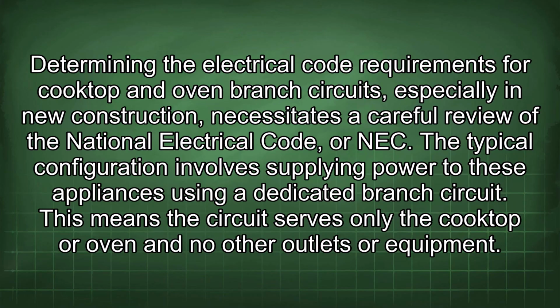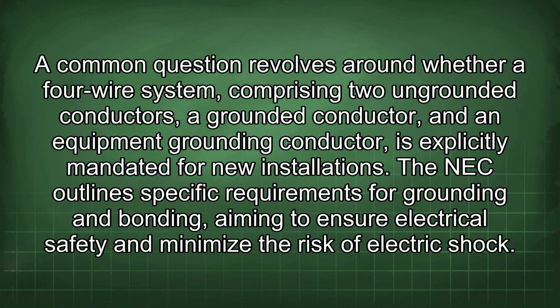Determining the electrical code requirements for cooktop and oven branch circuits, especially in new construction, necessitates a careful review of the National Electrical Code, or NEC. The typical configuration involves supplying power to these appliances using a dedicated branch circuit. This means the circuit serves only the cooktop or oven and no other outlets or equipment. A common question revolves around whether a four-wire system comprising two ungrounded conductors, a grounded conductor, and an equipment grounding conductor, is explicitly mandated for newer installations.